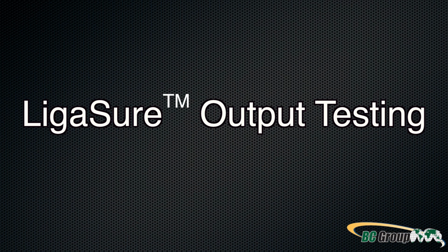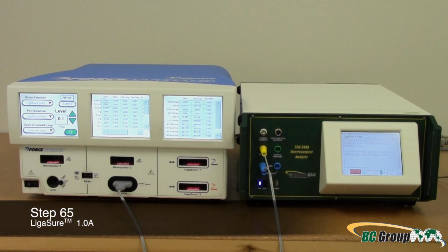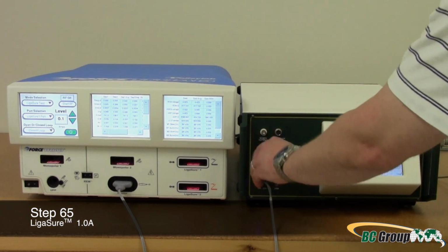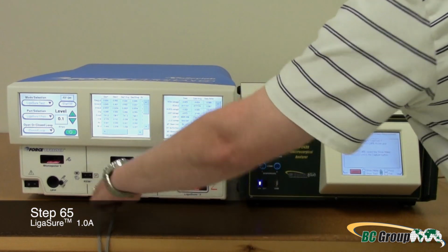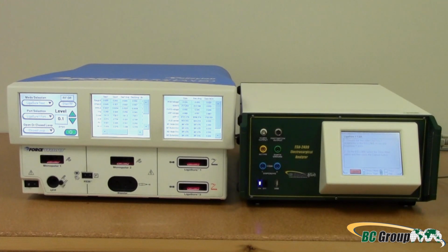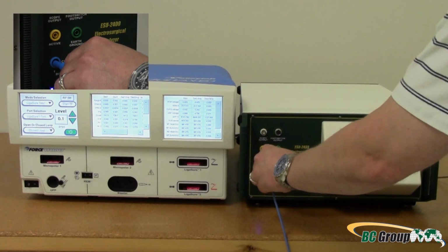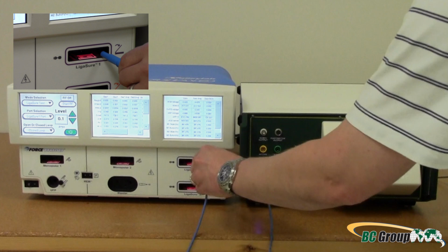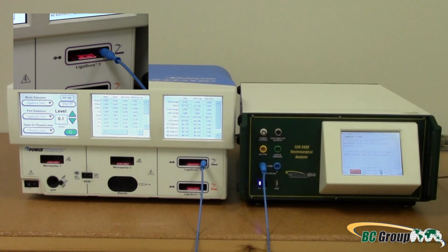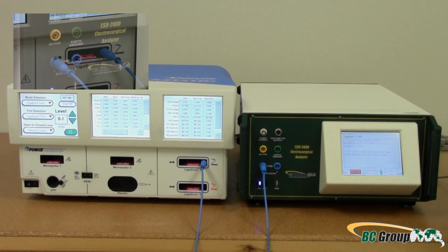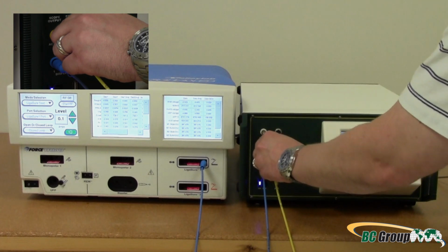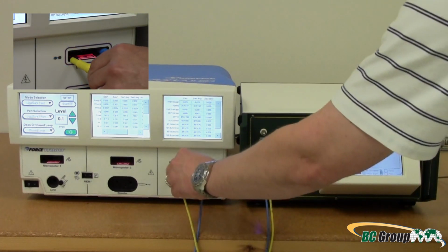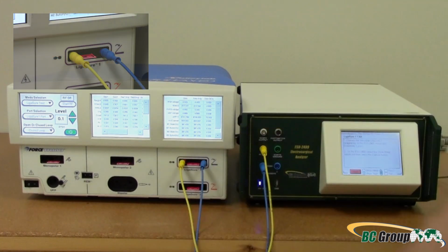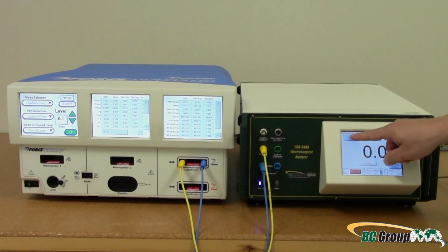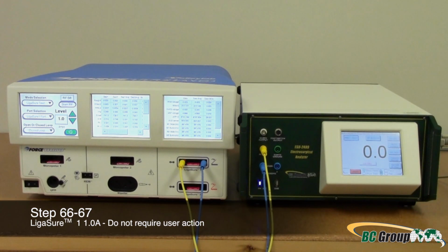LigaSure output testing. Step 65. LigaSure 1, 1 amp. Remove the autobipolar lead. Connect the 2 outer tines of the LigaSure 1 output to the ESU-2400 active and dispersive 1 ports. Select Show Meter and then press Capture. Steps 66 through 67 do not require user action.